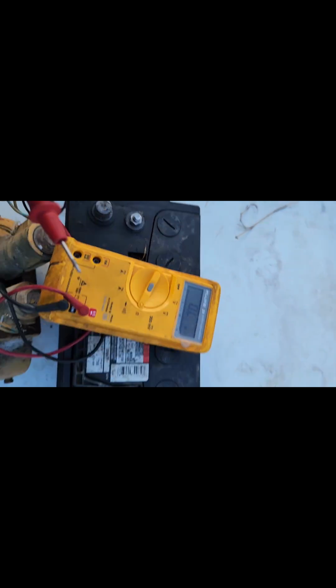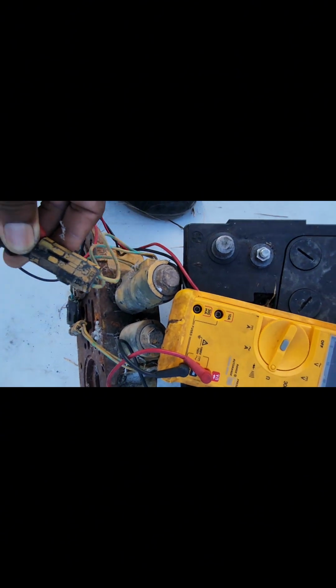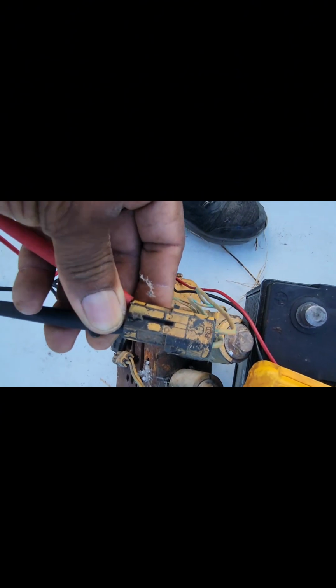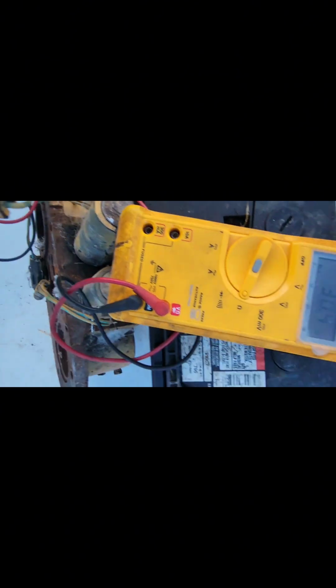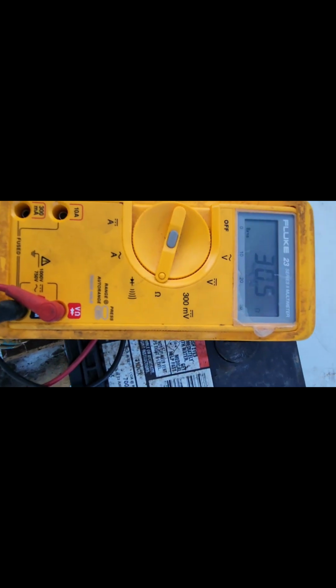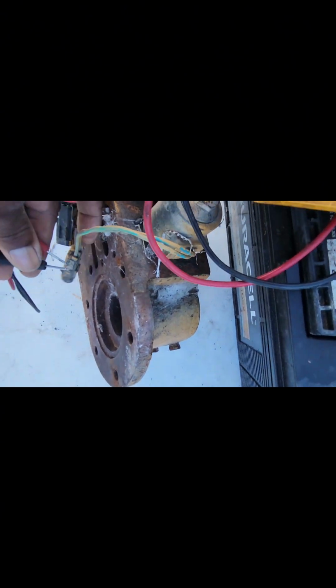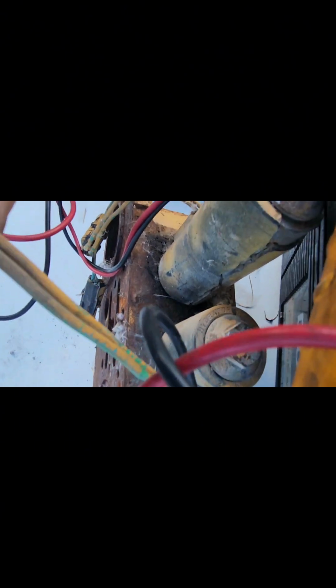You're going to take 2 of these. If you look at this coil, you see I have one lead on one pin and one on the other pin. It says 30 ohms. To know if 30 ohms is good, you check all 3. If you get 30 ohms on each one of them, then you know 30 ohms is good because they have the same part number and they all should read the same.